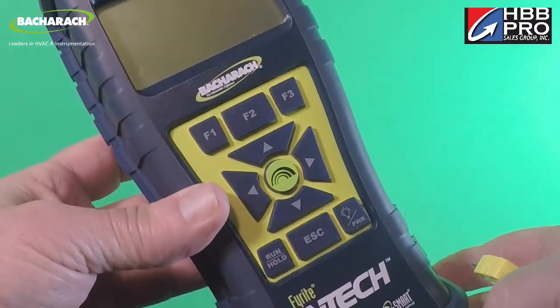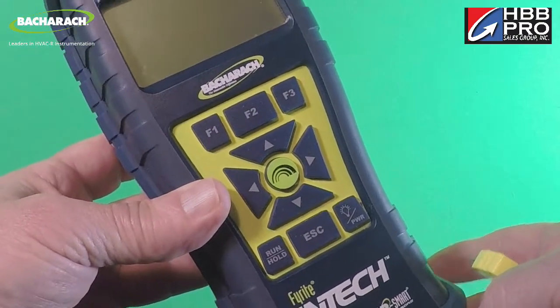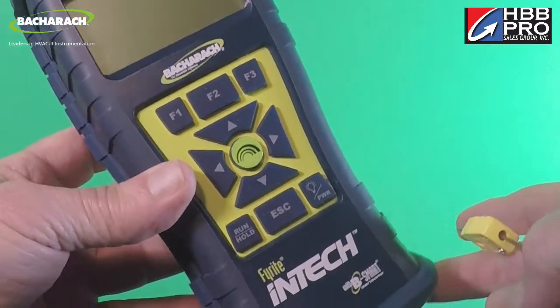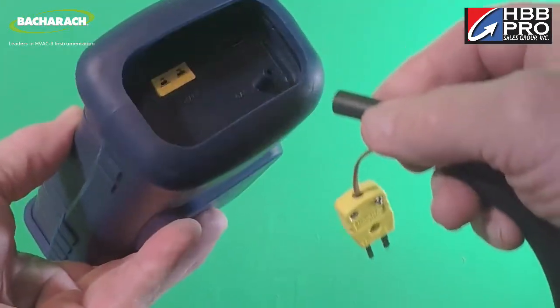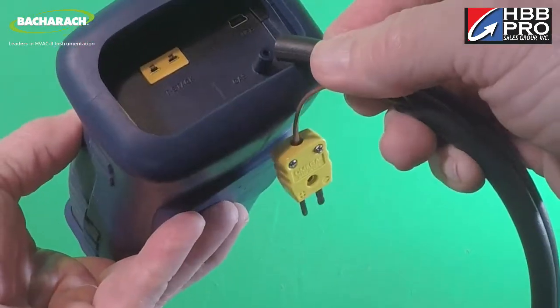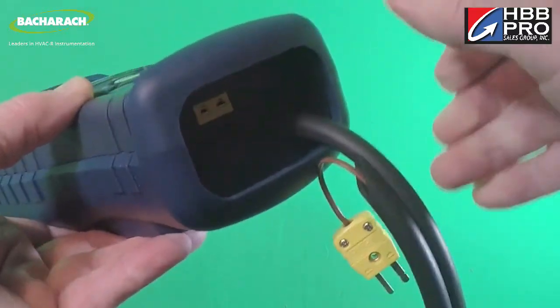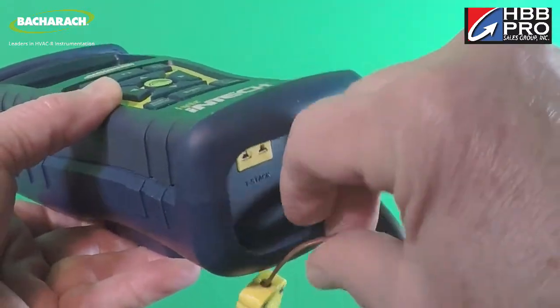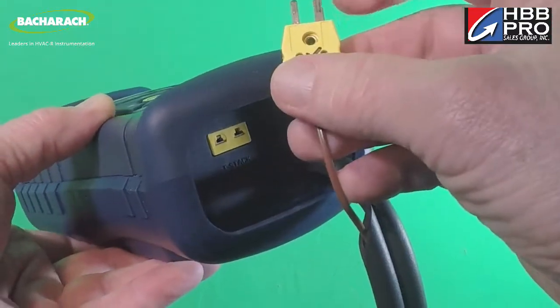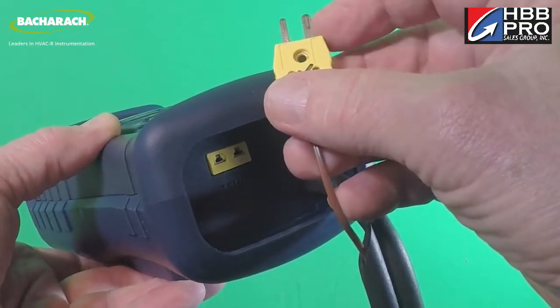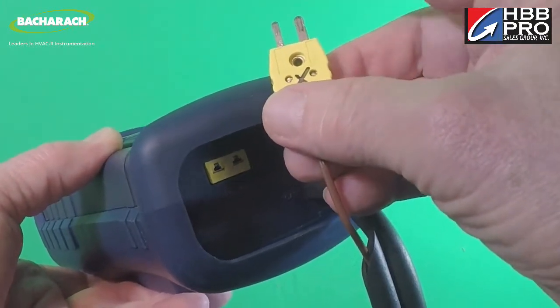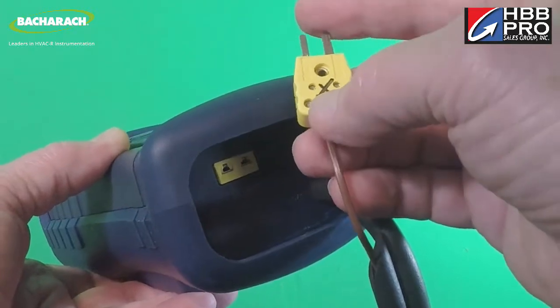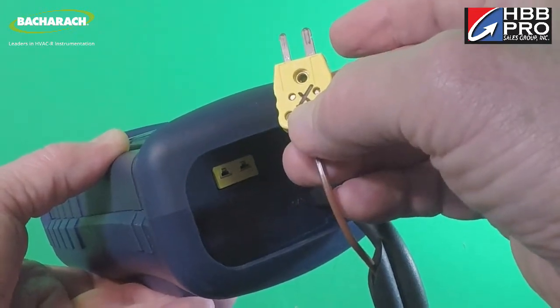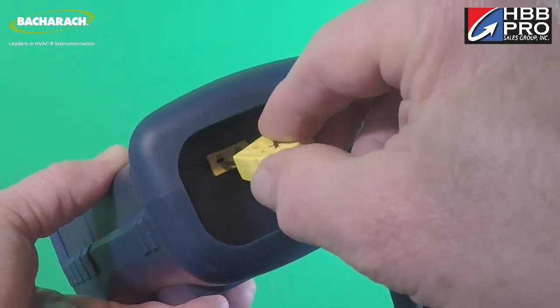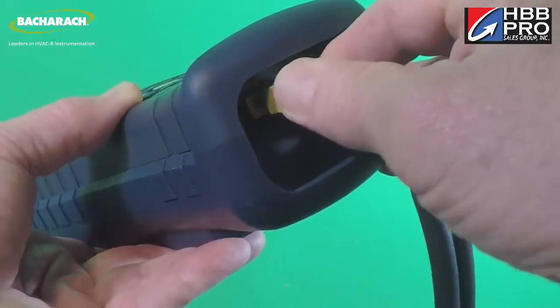Okay, before we fire up the equipment, the first thing we want to do is have the instrument up and running. So to get that going, we'll need to plug in the hose and probe assembly. Just slide that over the port. This is a K-type thermocouple. As a result, it has one blade that's a little bit wider than the other, just to make it a little bit easier to make sure that you plug it in with the right polarity. I'll just take a marker and put an X on the top of it, again, just to make it a little bit easier to get together.